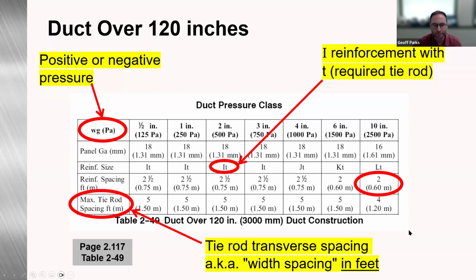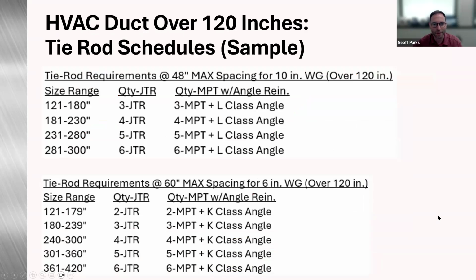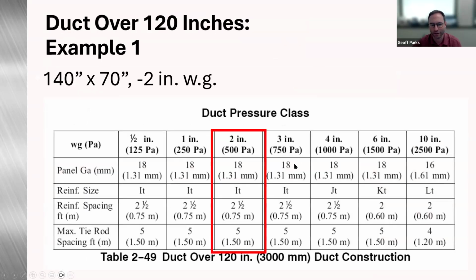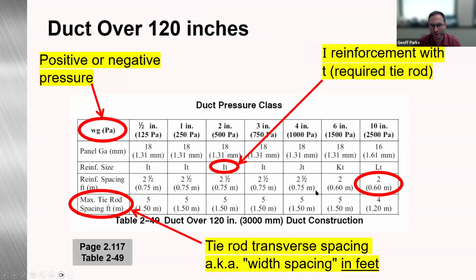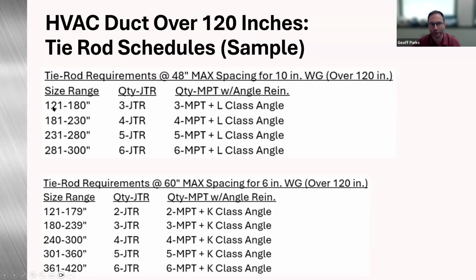And if you don't like doing math, I have created what I call a tie rod schedule. This is something that's not currently in the duct standard, but we're going to look to maybe add this in the next edition. It's basically taking this table here and building out your tie rod and reinforcement requirement for different size ranges. So be on the lookout for that one in the next couple years to make its way into the standard, hopefully.